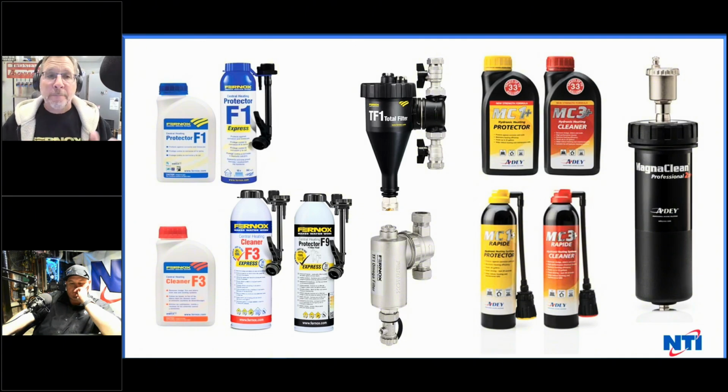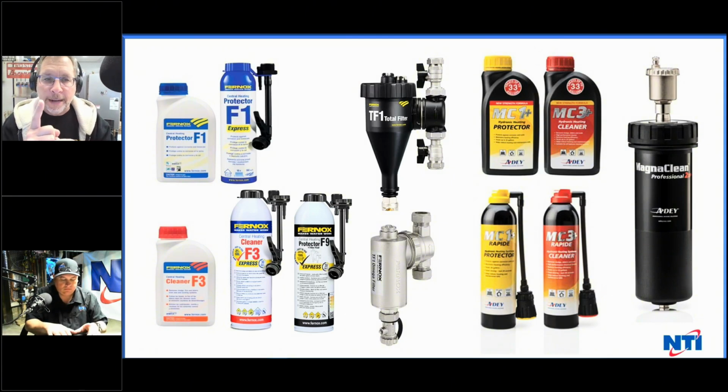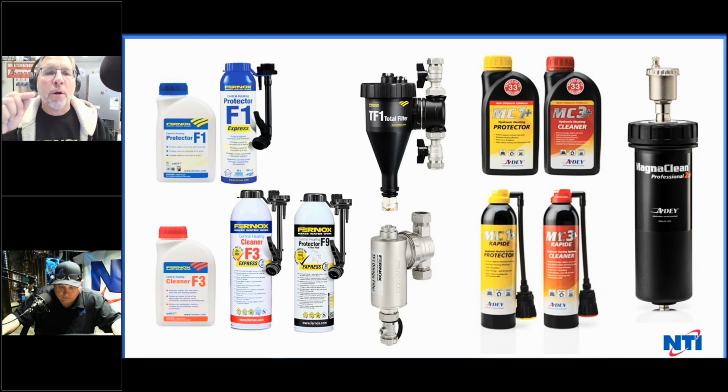They all have magnetic filters. They all have spinnable fittings, so you can put them vertically or horizontally. It doesn't matter. They come with ball valve options if you want them. So they're available. You just have to watch the flow rates on the magnets. Important: always watch your flow rate on the magnets. Don't overflow a magnet. Meaning if the magnet's rated to 14 gallons a minute, do not go over 14 gallons a minute or you can't get the magnetite out.